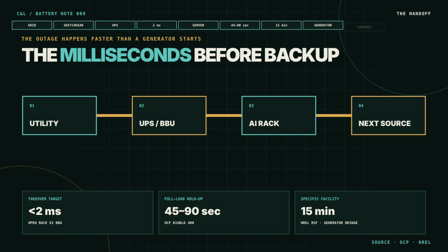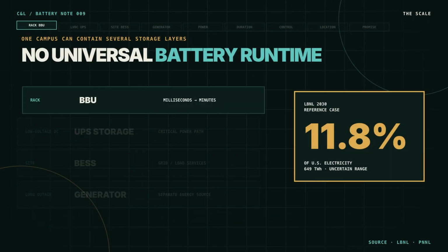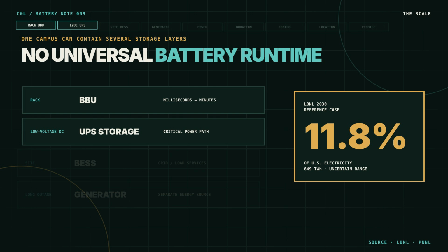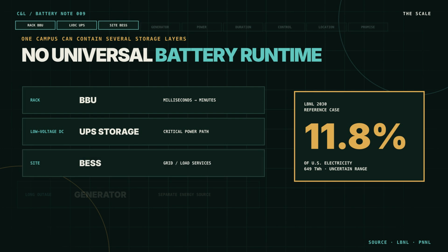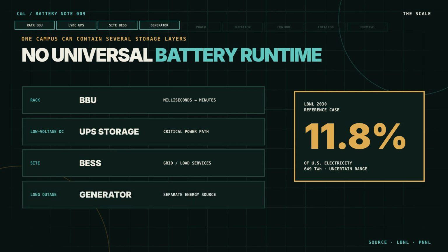The runtime depends on what must start next, how much load is protected, and where storage sits in the power path. This is why battery capacity alone is a weak purchasing metric. The design also has to specify response time, protected load, power quality, handoff logic, and the failure mode if any link between the cell and the server does not respond. AI changes the scale and behavior of the load, but it does not create one standard battery recipe. Berkeley Labs' 2026 reference case estimates U.S. data centers could use 649 terawatt-hours in 2030, or about 11.8% of U.S. electricity, with a wide uncertainty range.